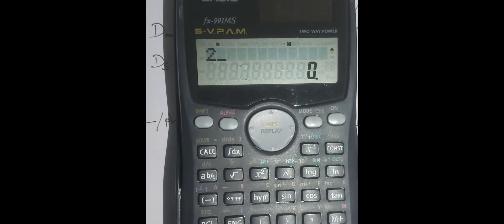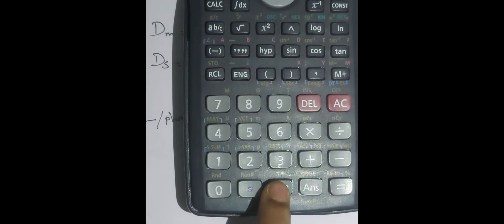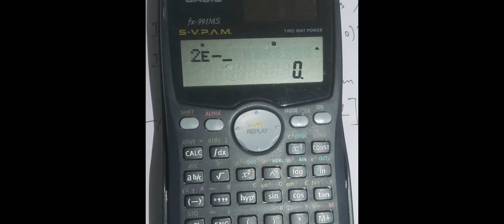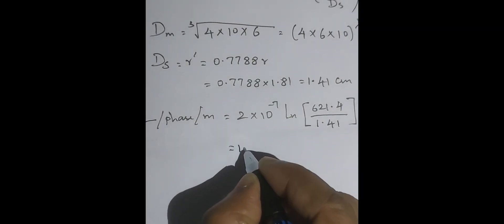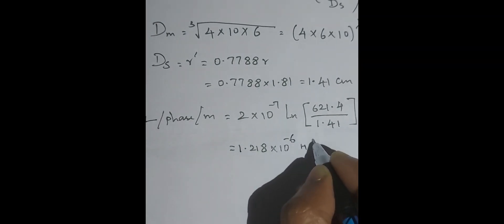Substituting: inductance per phase per meter = 2 × 10⁻⁷ × ln(621.4 / 1.41). Using the calculator — press the exponential button to enter e to the power −7, then multiply by ln(621.4 / 1.41), close the parenthesis. You will get 1.218 × 10⁻⁶ Henry per meter.